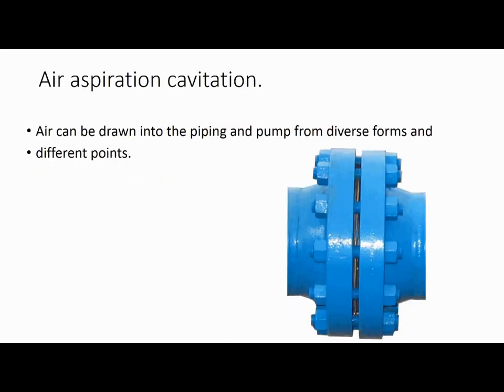Air aspiration cavitation: air can be drawn into the piping and pump from diverse forms and different points. The air can come into the pump through the pump shaft packing, valves and packings in the suction piping, joint rings in the suction piping, flat face sheet gaskets at pipe joints, and threads of fittings and instrumentation in the suction piping.